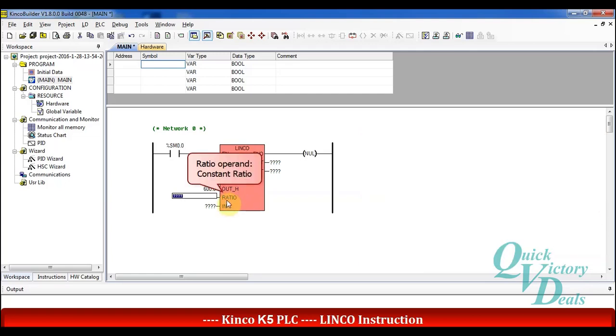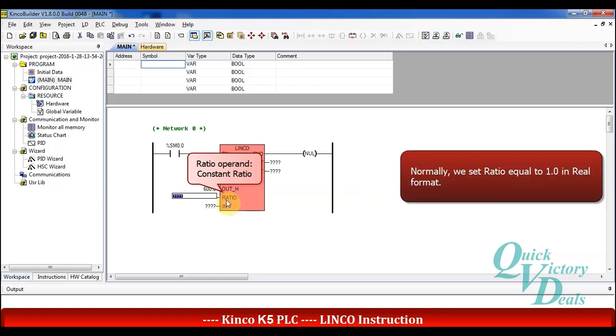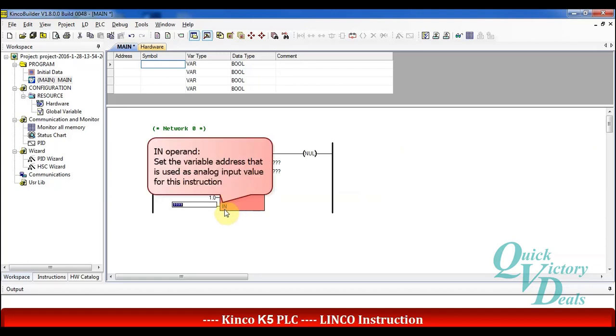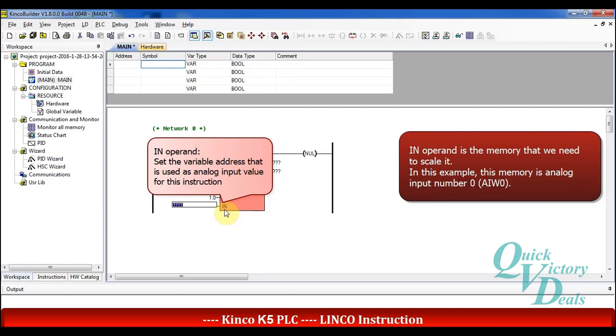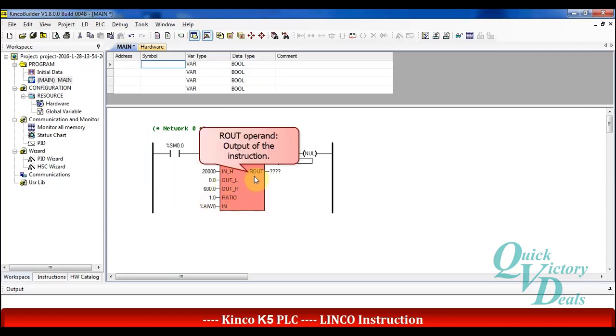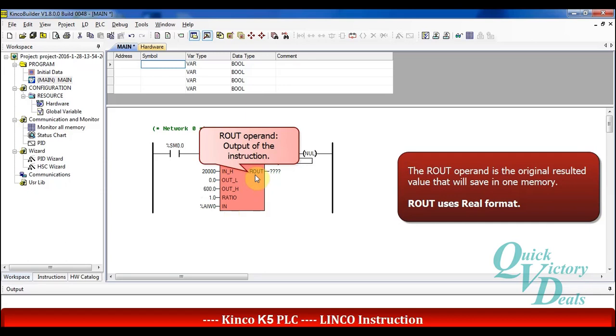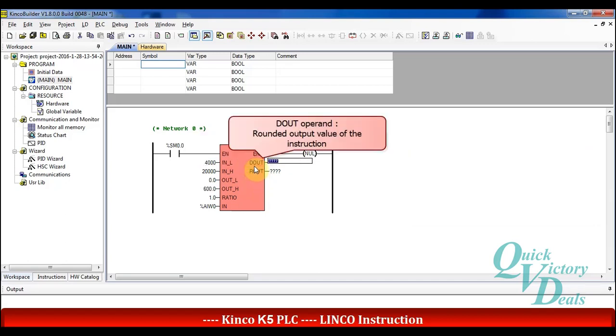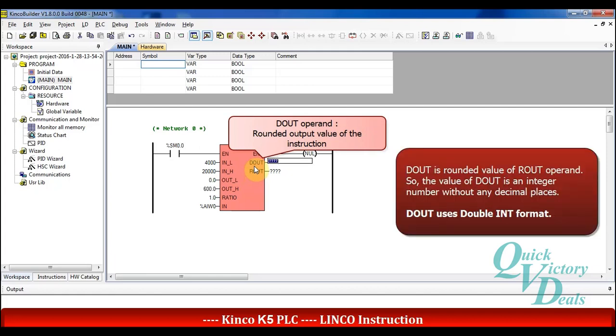The ratio operand is a constant ratio, and normally we will use 1 in real format. In the IN operand we will set the memory that includes the source value we want to scale — here we are using channel 0 of the analog input, or AI word 0. The function saves the result in the ROUT operand in real format, and we also have a rounded value of ROUT in the DOUT operand with double integer format. So we will assign separate memories for these two operands.